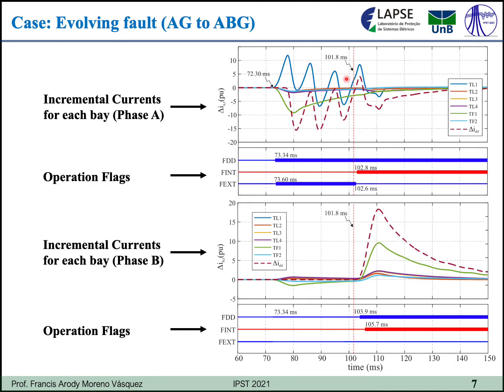Here, in this case, an external fault initially occurs at this instant in phase A at feeder TL1, transmission line 1, and it causes the saturation of the corresponding CT. After that, the fault evolves to an internal fault at this instant here, now involving phases A, B, and the ground.